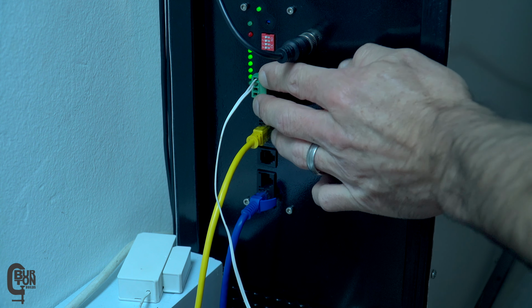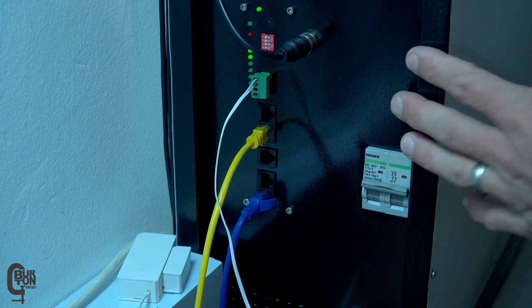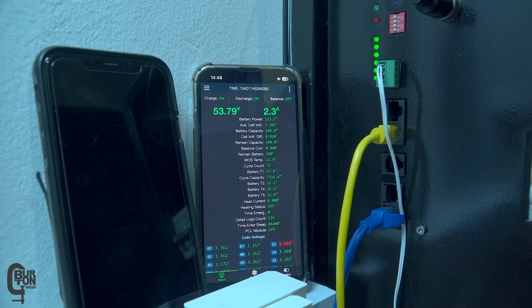So we've got it plugged in and it's powered up, and it should be working now. The phone on the left is my normal daily use phone, and the phone on the right is showing the BMS app, connected to the master BMS and the battery you're looking at. I also have the dry contact trigger, or relay number 1, set to close when a BMS system alarm is triggered, which we saw in a previous video.